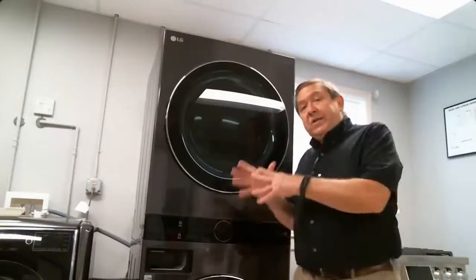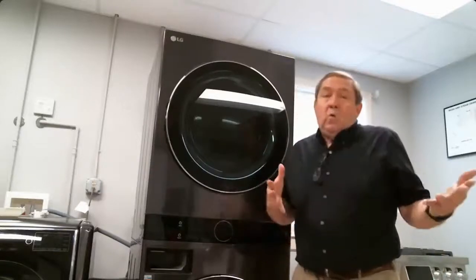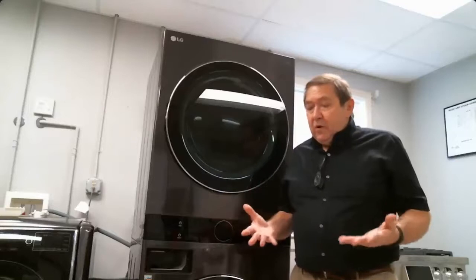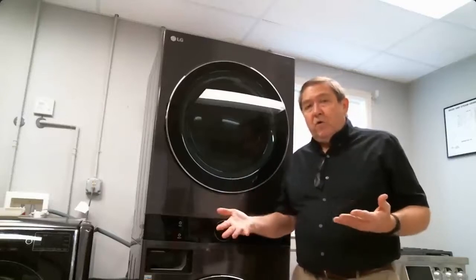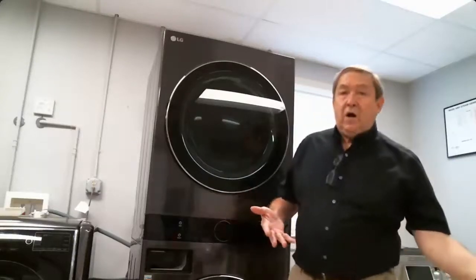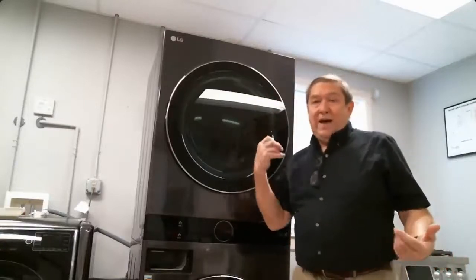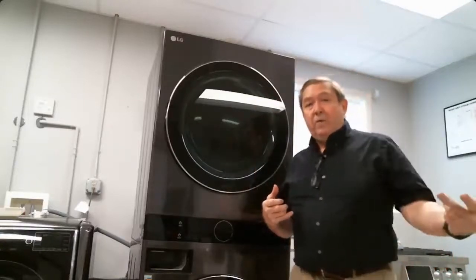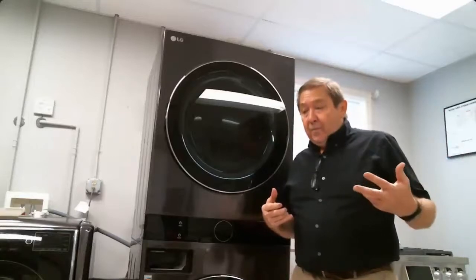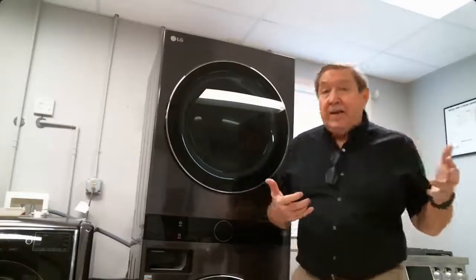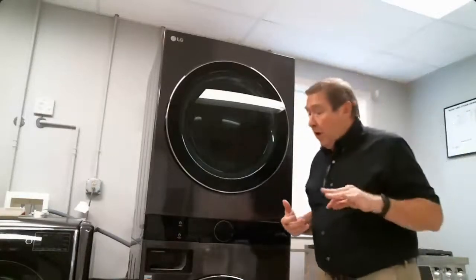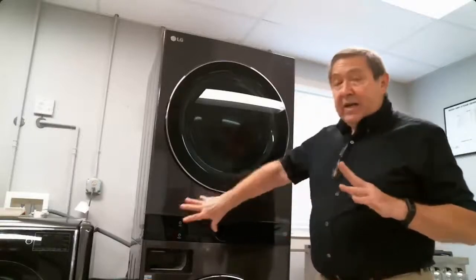So that's why I always say check from the main board, because technically, when we're using the hall sensor, we're using 12 volts DC. We're sending that down to the hall sensor, but we need a signal back. So our signal back comes from the red and the blue wire, and it's typically pulsating about 11 volts back to the board. So the idea is checking at the main board.